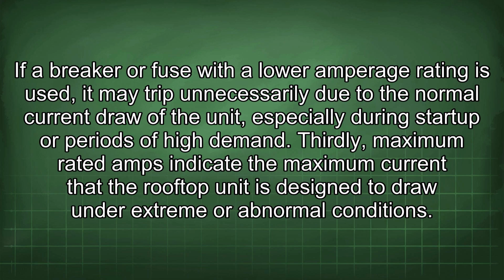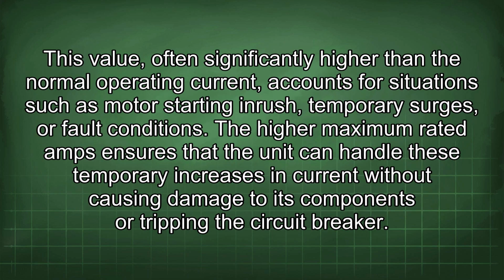Thirdly, maximum rated amps indicate the maximum current that the rooftop unit is designed to draw under extreme or abnormal conditions. This value, often significantly higher than the normal operating current, accounts for situations such as motor starting inrush, temporary surges, or fault conditions. The high maximum rated amps ensures that the unit can handle these temporary increases in current without causing damage to its components or tripping the circuit breaker.